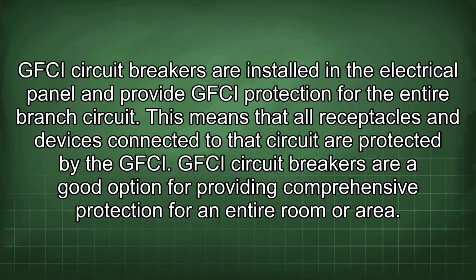GFCI circuit breakers are installed in the electrical panel and provide GFCI protection for the entire branch circuit. This means that all receptacles and devices connected to that circuit are protected by the GFCI. GFCI circuit breakers are a good option for providing comprehensive protection for an entire room or area.